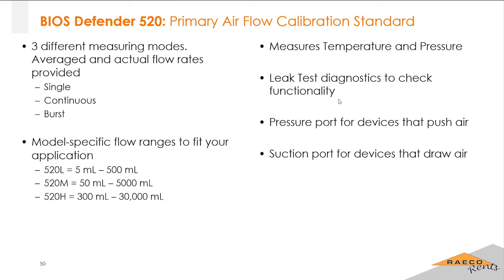It also has leak test diagnostics to check the functionality, make sure there's no internal leaks, and that you're not getting bad readings on the calibrator. Another interesting thing is that it has 2 different ports, one for pressure and one for suction. So if you happen to be trying to calibrate, I don't know, a regulator that's pushing air, I've never had anybody utilize that feature that I know of, but just another little thing that the Defender can do.